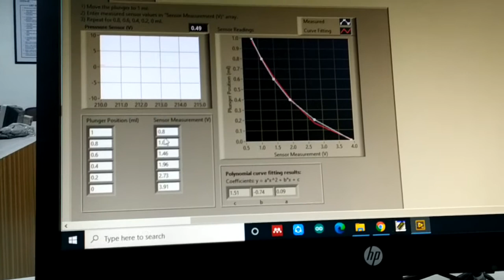Now you see at the top you have 1, at the bottom you have 0. At 1 it is completely not pressurized at all, so that's why you see a very minimum reading of 0.8 volt. As soon as you move from 1 to 0, there is an increase in the voltage value, because as I move towards the 0 end, I am pressurizing the sensor, compressing this plunger position. So more and more pressure means more voltage.